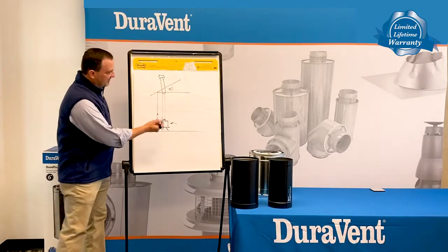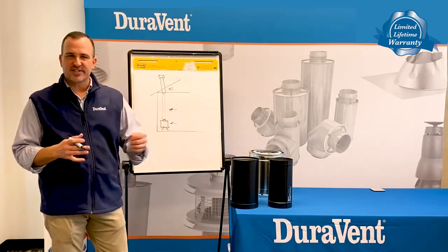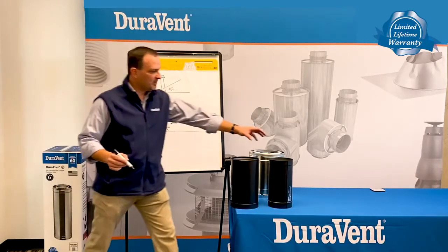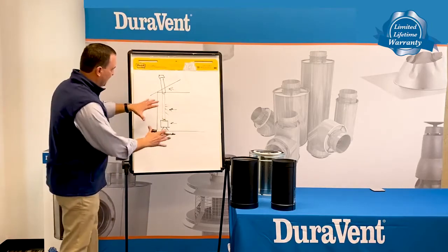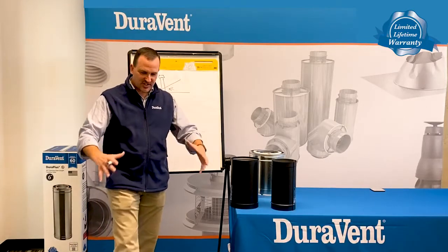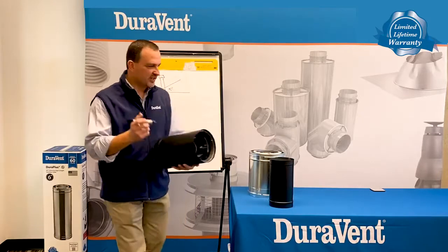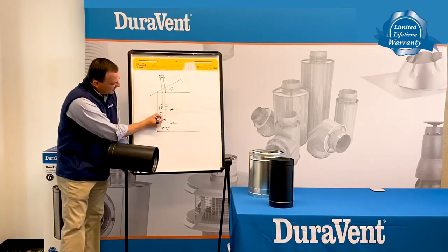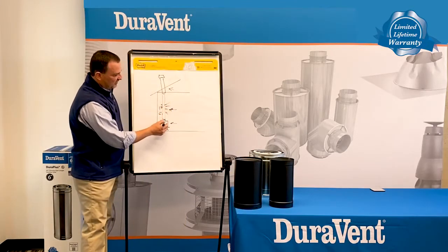The reason there are two different variations is that single wall is actually an older product, designed back when stoves were inefficient. We needed heat to be captured from the connector pipe, so people would put single wall connector pipe in to gain some more heat being lost as it exhausted out of the house. Today's stoves — anything 2020 or greater — are actually so efficient that we really don't want to capture heat anymore out of the single wall black pipe. That's why we have a double wall, close clearance product. A single wall product has to be 18 inches from the wall, while this product is only six inches from the wall.